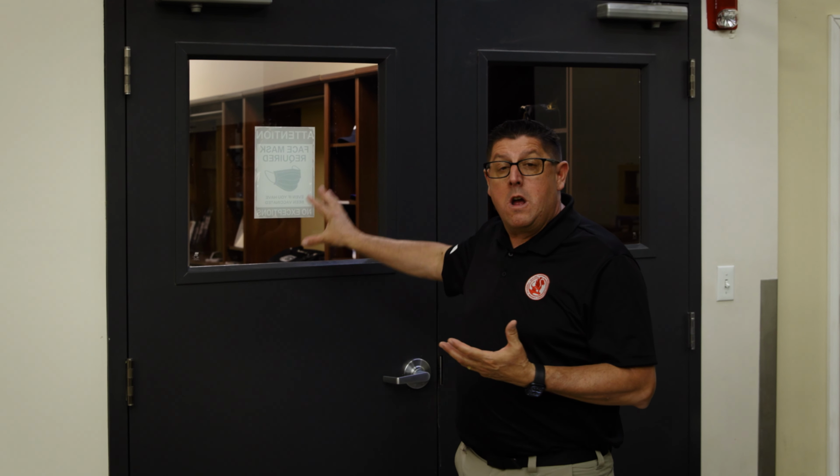One other thing you should look at is glass. In this case, this is an older door. This glass is a tempered glass. You're not required to identify tempered glass. In a modern fire separation door, this would actually be wired glass. So I would look for wired glass, hinges, latches, closures, and lastly, labels.